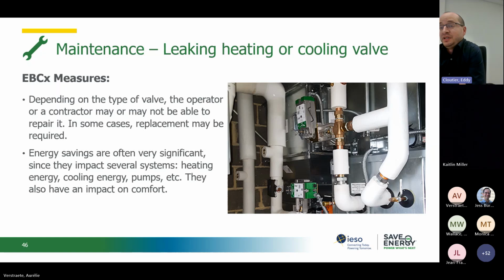So what would be the EBCX measure? Of course, depending on the type of valve, the operator or contractor may or may not be able to repair it. And in some cases, replacement might be needed. Energy savings are often very significant in that case, since they impact several systems: heating energy, cooling energy, pumps, etc. They also quite often have an impact on comfort.